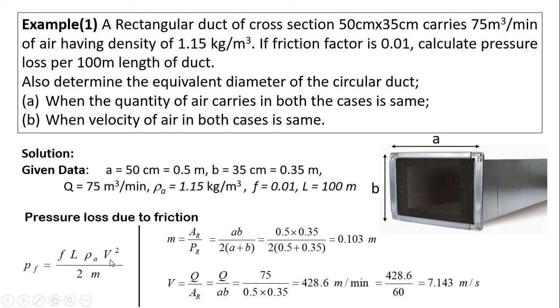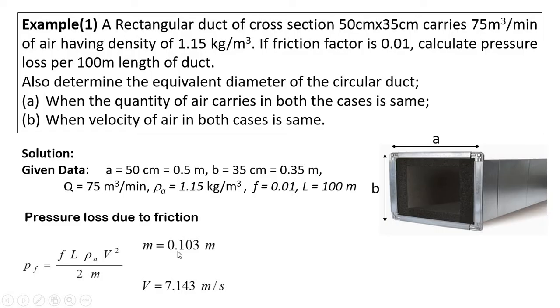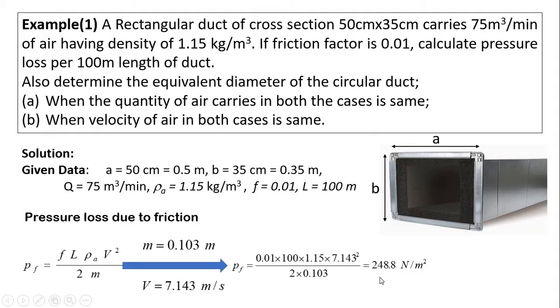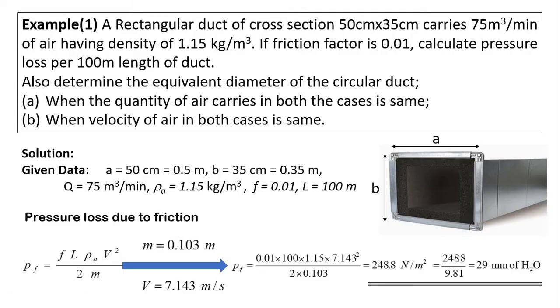Now all values in the formula are known. With m = 0.103 m and v = 7.143 m/s, by putting all values we get pressure loss due to friction Pf = 248.8 N/m². We can convert this pressure loss to mm of water column by dividing by 9.81, which gives 29 mm of water column.